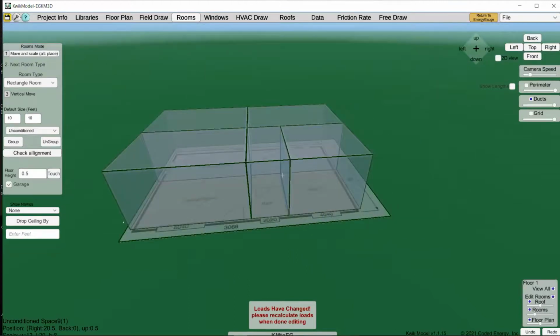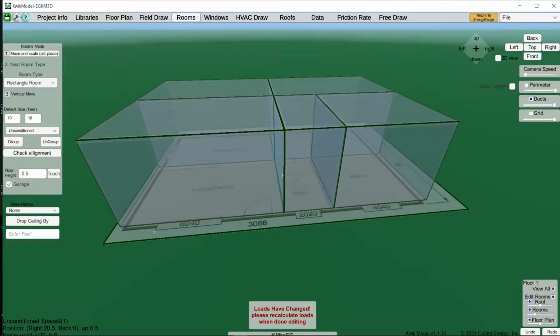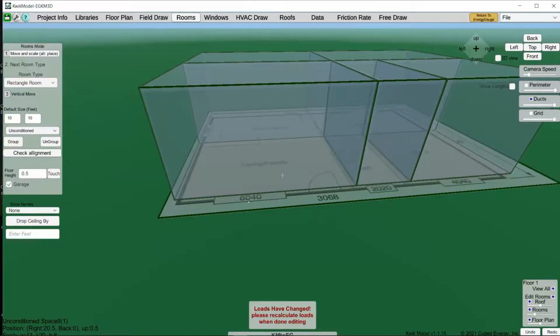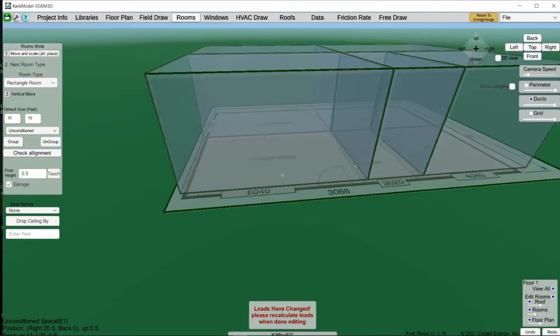So now the software knows the size of each of these walls, and in the data tab, it's tabulating all those areas. It's creating wall names. It's giving them the default wall types. We'll get to that in just a second. The next step is to now put windows on here. And so you'll see in the plans, there's these windows, 6040, 2020. Those are pretty standard architectural nomenclature for windows. You'll see them written slightly differently, maybe 6/0 x 4/0 or something like that. But it basically means 6 feet, 0 inches wide by 4 feet, 0 inches tall. Very common architectural nomenclature, okay?